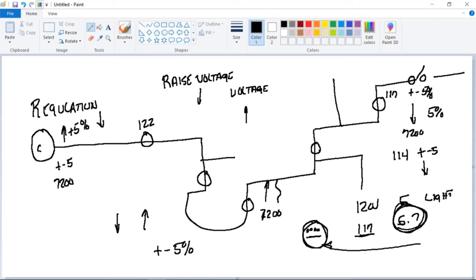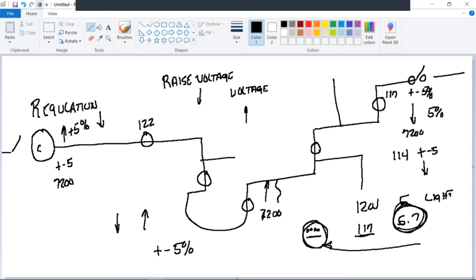Okay. When you've got the first open point on the, let's say like this, let's hold on. Say you've got your open point on that line side disconnect. Some organizations do design it this way. They'll go ahead and put the disconnect on the other side. So let me just draw that in red. They will put a disconnect there. If they do not, it's just some manual unbolting. Just unbolt the conductor from the feeder line to the regulator. That gives you a new open point because there's no load. Load can't go anywhere. So it's just a regular unbolting of the regulator.